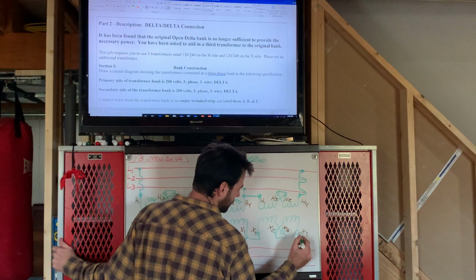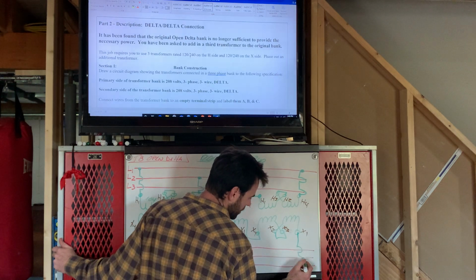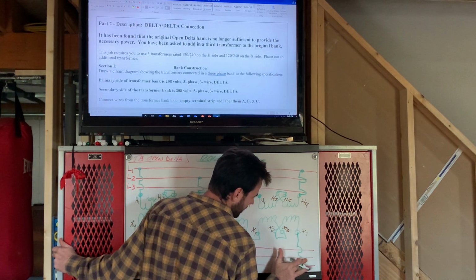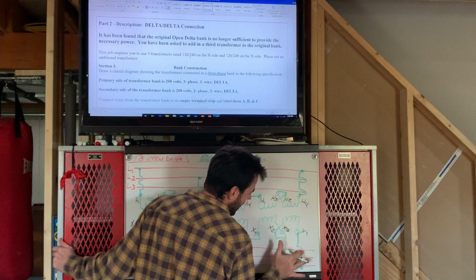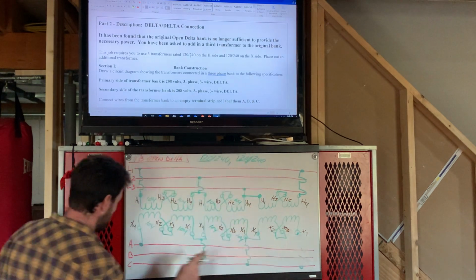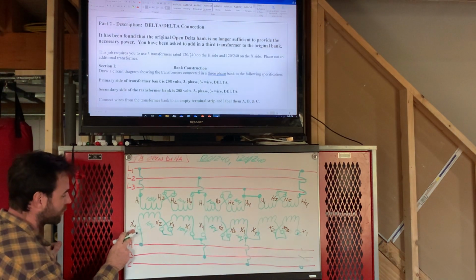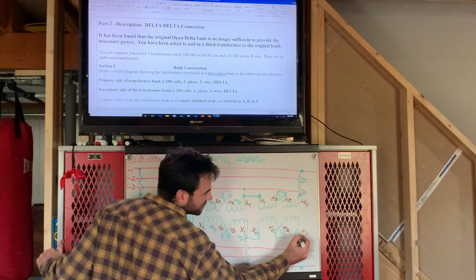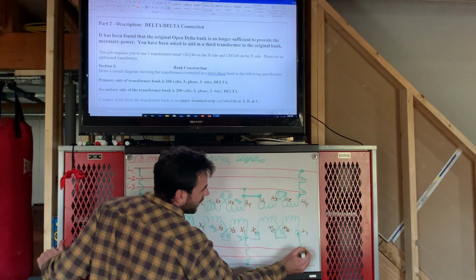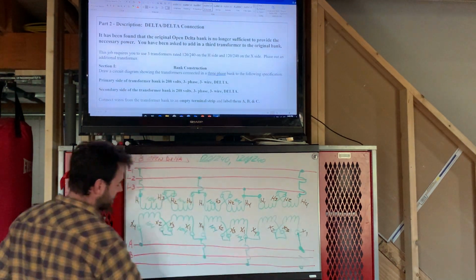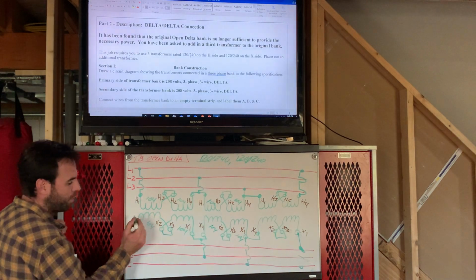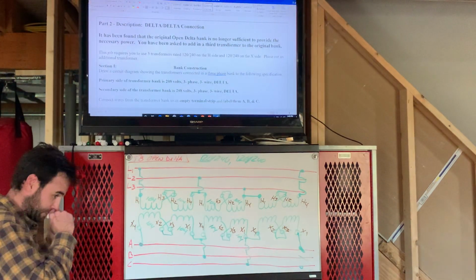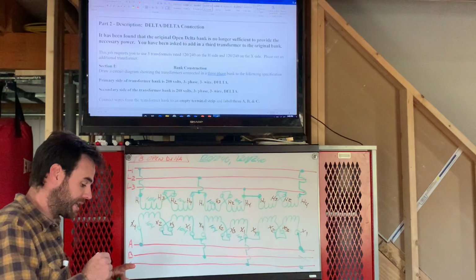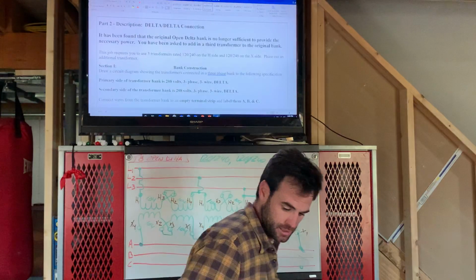And then I'm just going to take X1. Oh, I'm sorry, went to the wrong one. You're going to tie X1 to X4 of transformer 1, which is actually the A phase. I thought it was the C phase. My bad, guys. X1 of transformer 3 gets tied to X4 of transformer 1, which is our A phase. All right? So now I'm going to jump into how you're going to derate this.